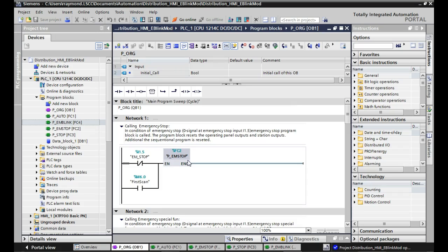Right? You understand? So back in Allen Bradley, I drop it down. You would have to remember the file number that you assigned that subroutine. So your JSR doesn't use a name for RSLogix. You specify a file number that it's supposed to jump to. And what they do in Siemens is you just give it the same name. In fact, guys, all you have to do to jump to a subroutine is you set up your rung, you come up here, you grab the subroutine you want to come to, and you drag it and put it on there. That's all you have to do. And once you give the subroutine a name, that's how you use it. So you don't even have to enter that instruction. There's no JSR instruction in the palette. Because how do you add a subroutine?